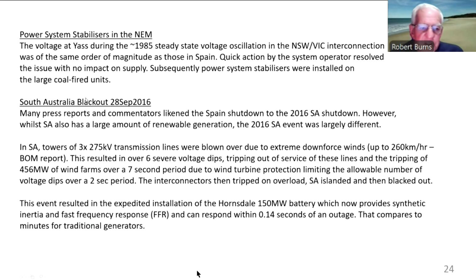They're just back on these power system stabilizers. Well, back in 1985, we had a steady state voltage oscillation between New South Wales and Victoria, and it was the same sort of magnitude of the voltage variation. In our case, the system operator resolved the issue with no impact on supply, but subsequently we installed power system stabilizers on all our large coal-fired units, such as Bayswater, Liddell, Mount Piper, and down in Victoria at Loy Yang and so on.